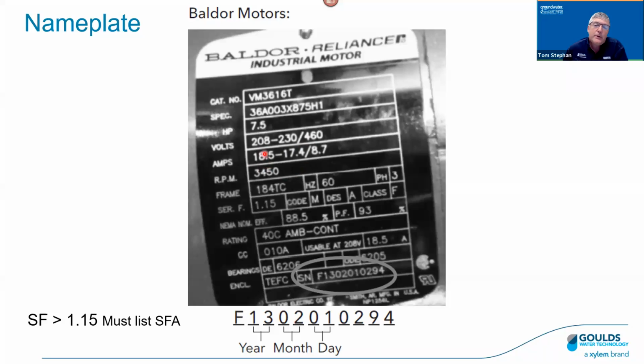Now the amperage here corresponds to the voltage. Again, it's not service factor amps, it's just amperage, and it just corresponds to voltage. So if you are operating at 230 input and we've wired it properly, in this case to low voltage, the amperage is 17.4. RPM, 3450. The frame size has to do with the size of the motor. We can see it's a 60 hertz motor, and it is a 3-phase motor.